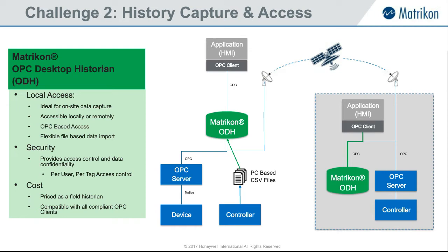and there are different modes. So whether it's used more as a buffer, that concept of a circular buffer, therefore you have zero maintenance because you identify how much space it's going to take, and it basically just continues to capture data for the amount of time that you would like to have history for, and then it just overwrites it. So therefore you don't have to do maintenance on that installation. It just continues to run indefinitely. So that's the purpose for ODH.